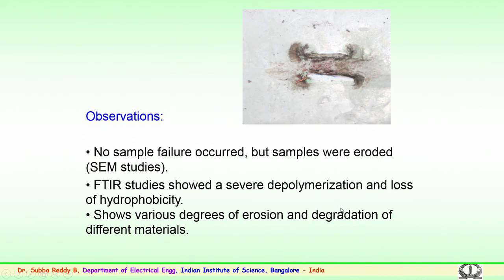So, this is how some of the observations were: between the electrodes there is an erosion observed on the sample, but no sample failure occurred during the process. All the samples were observed to be eroded when the scanning electron microscopy studies were carried out, and the Fourier transform infrared studies showed severe depolymerization and loss of hydrophobicity, particularly the water repellent activity of the rubber. This was observed after the experimentation, and the studies also showed that the degree of erosion, the depth of erosion, and the changes on the surface were different for different types of materials. We have tried to use several types of materials including the liquid silicone rubber. So, the degradation was different for different types of materials in this study.